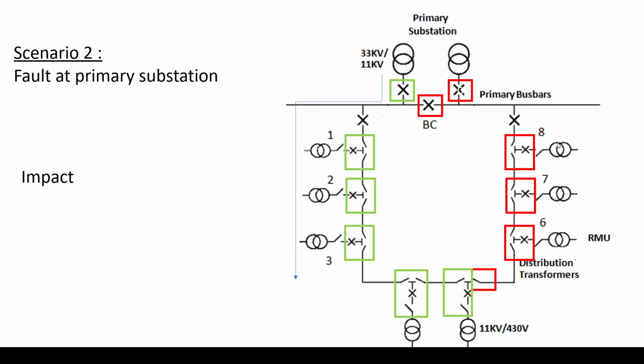but due to the fault here, the power have disconnected to all these loads. So how the RMU would help us to overcome this and to ensure continuity of the power supply? As we have mentioned, one of the main reasons why the RMU and the advantages of the RMU, why it's used in all projects, is to provide redundancy and to ensure that the power is available in case of faults happening at several locations of the network. So let's see how the RMU would help us to overcome this. What would happen in this case is that the bus coupler in the primary substation would close. The bus coupler was open earlier.